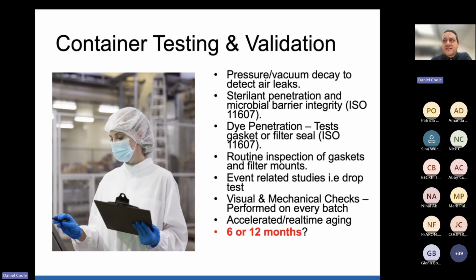What sort of things are we testing when we're manufacturing, testing and validating containers? Well, you're looking at things like pressure decay to detect air leaks. Obviously, that is not something you want when you've got a container. You hope that it's sealed and it won't leak air and potentially bugs. Then sterilant penetration and microbial barrier integrity, as directed by ISO 11607. Dye penetration tests. Of course, routine inspection of gaskets and filter mounts, and I'm going to give you a bit of guidance on that later on.